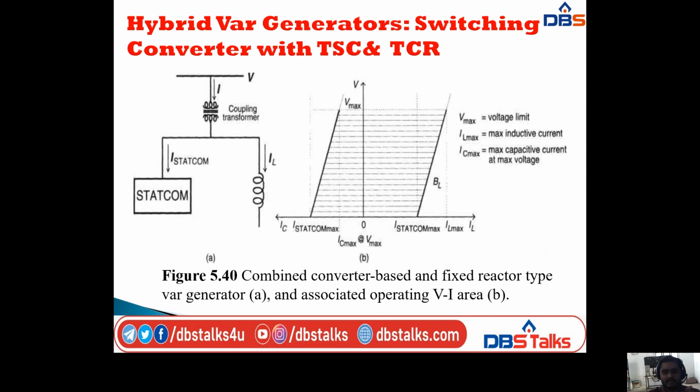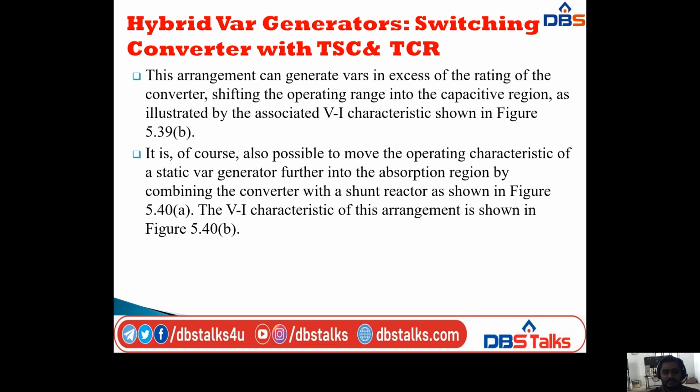Here I am taking the combined converter based and fixed reactor type. Previously we took the combined converter based and fixed capacitor type, but here I am taking the combined converter based and fixed reactor type. It is possible to move the operating characteristics of a static generator further into the absorption region by combining the converter with a shunt reactor. The VI characteristic of this arrangement is shown in this one.